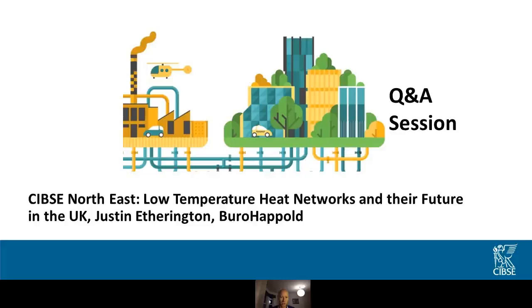Also doing some work at the moment with Plymouth, looking at heat pump deployment and seeing what we can do with weather compensation and heat pumps that can achieve a higher flow temperature on an individual basis. We're finding that with weather compensation across the year, quite a lot of existing systems can be retained with manageable amounts of energy efficiency work. That's something we're beginning to get a better understanding of.